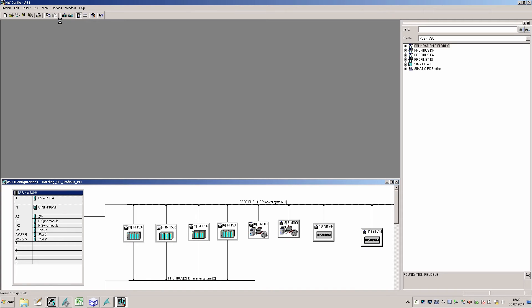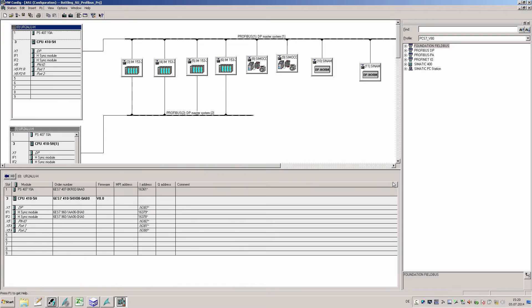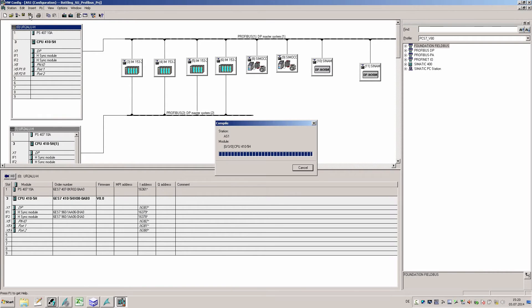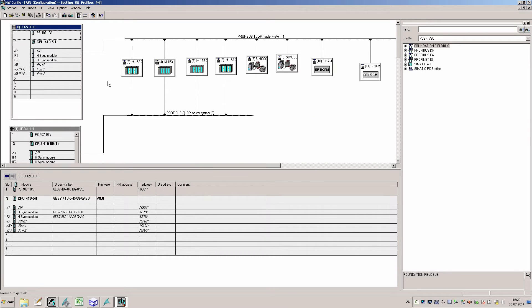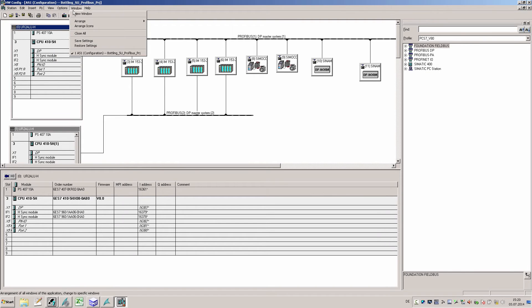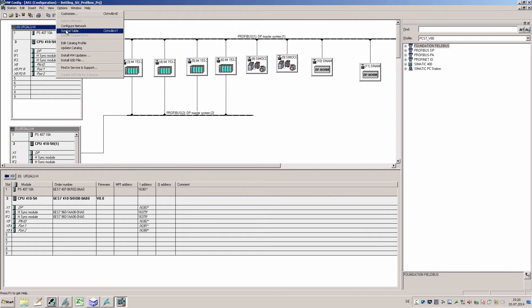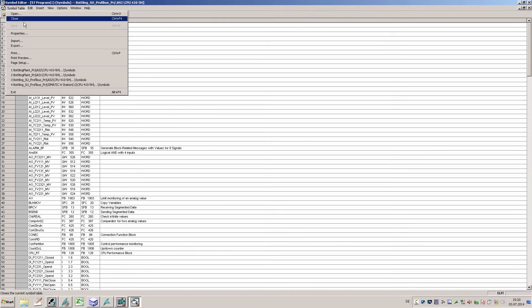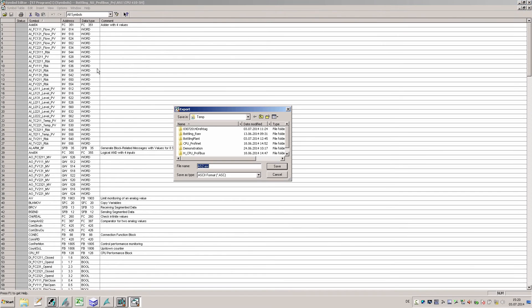Firstly I go to the hardware configuration function of the SIMATIC manager and click on Save and Compile. This creates the system data blocks that I need for the import process. By exporting the symbol table from the hardware configuration I can also transfer the symbols for the IO signals into the simulation.